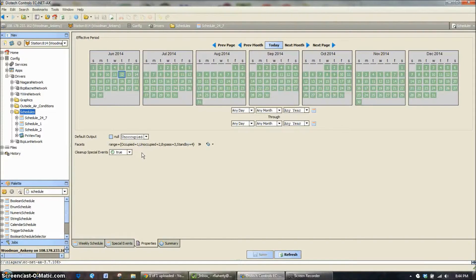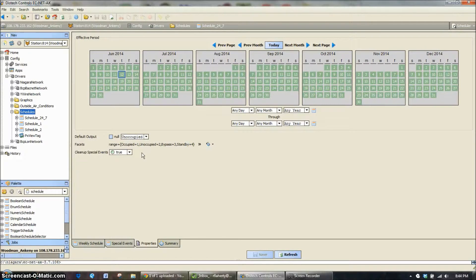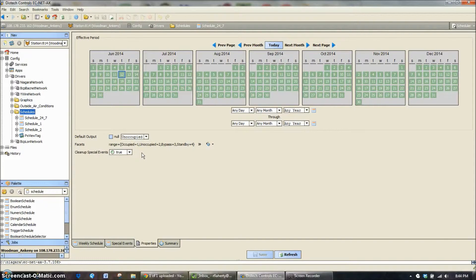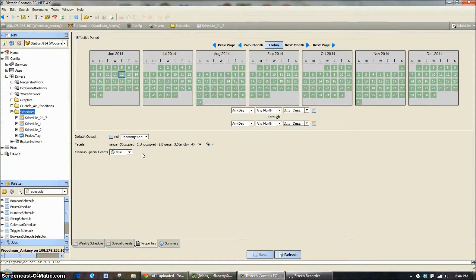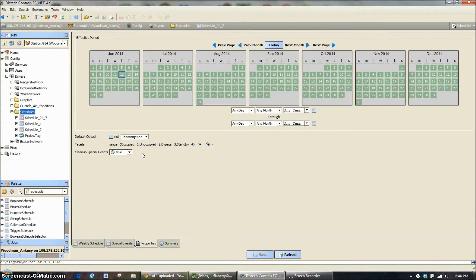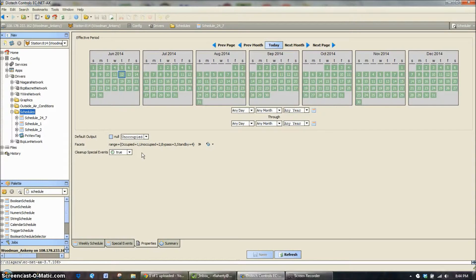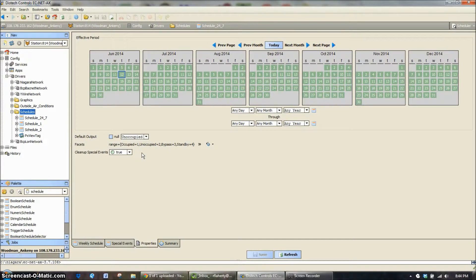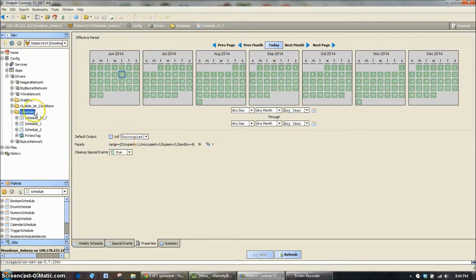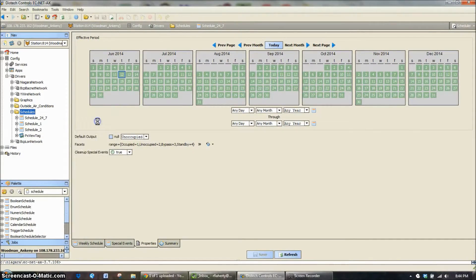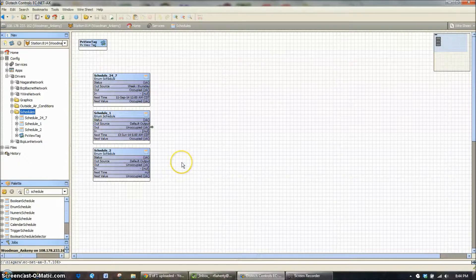Unoccupied, exactly what you would think, no one's there, maintains unoccupied set points. Bypass would be a mode where someone has pushed an override button in a room, or possibly you could even have set up with occupancy sensors. And then standby mode is a mode where there's no ventilation but we're maintaining close to occupied set points in the event that someone has walked out of a room just temporarily and we go back to occupied when the occupancy sensor picks them up.